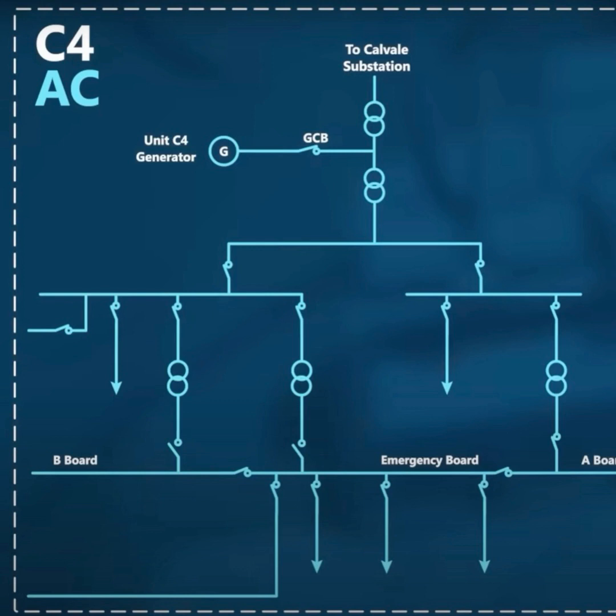But there's still something in the CS Energy report that's unclear to me. From the report, it states that the ACS not changing over, and I quote, "prevented the recovery of the DC supply to the Y generator protection system. However, even if the ACS had operated, it would not have resulted in supply to the emergency turbine lubrication oil or the emergency sealing oil pump, and therefore it is unlikely that it would have prevented the turbine bearing damage."